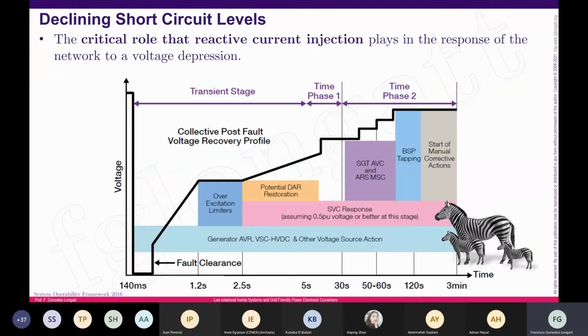What are the possible solutions? The idea is to try to use some elements that allow short circuit injection in order to try to recover the voltages, to create some contribution during the fault, and very important, improve the voltage recovery after the fault.